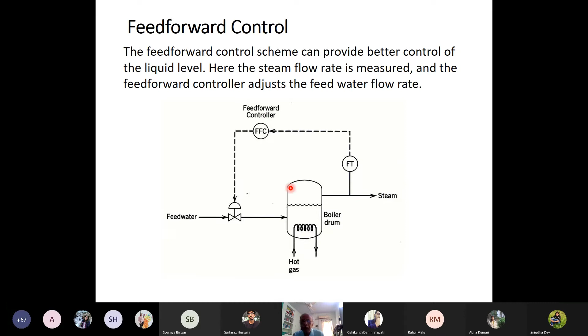So if the steam flow increases, you increase the feed water flow. If you increase the feed water flow, the bubble generation over here will stop, because the cold feed water is coming into the system and the level will remain the same. But the problem over here is designing this feed-forward controller. The feed-forward controller requires the process model. It cannot be a conventional PID controller. It requires knowledge of the process model.